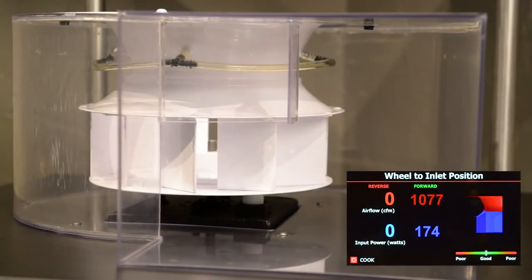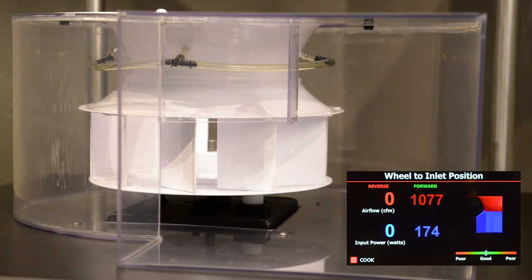Now, let's take a look at how improper wheel rotation affects fan performance. This is the number one cause of low system airflow, improper wheel rotation. The wheel shown here is a backward inclined wheel, sometimes referred to as a BI wheel.